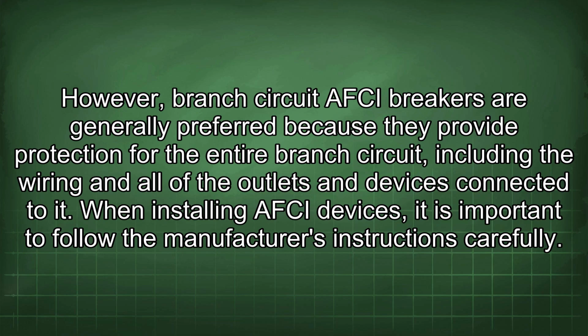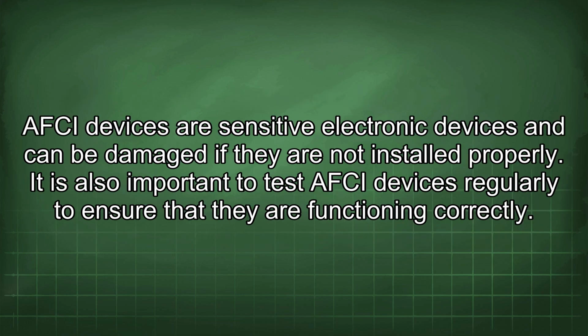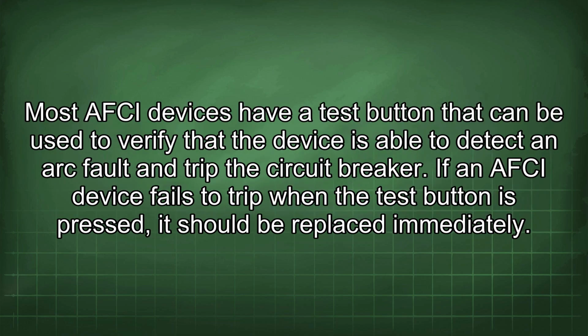When installing AFCI devices, it is important to follow the manufacturer's instructions carefully. AFCI devices are sensitive electronic devices and can be damaged if they are not installed properly. It is also important to test AFCI devices regularly to ensure that they are functioning correctly. Most AFCI devices have a test button that can be used to verify that the device is able to detect an arc fault and trip the circuit breaker. If an AFCI device fails to trip when the test button is pressed, it should be replaced immediately.